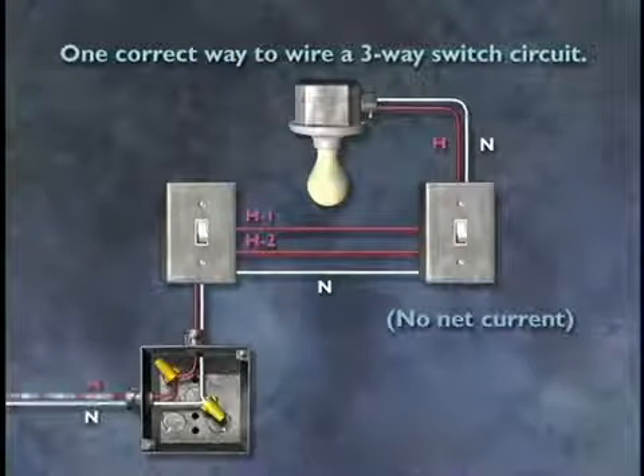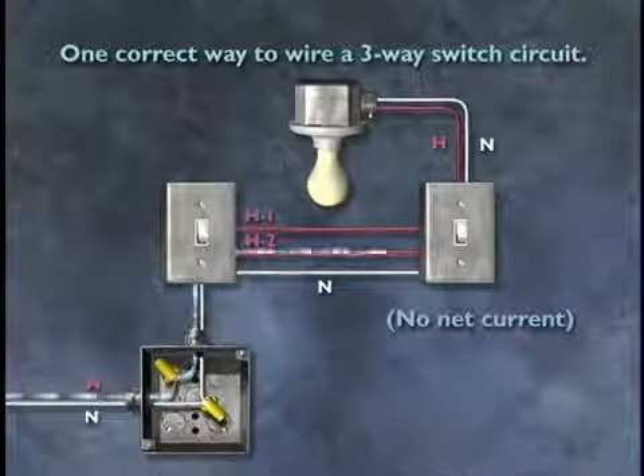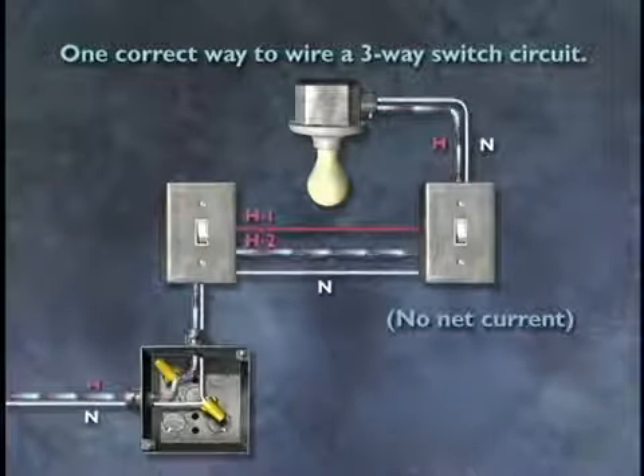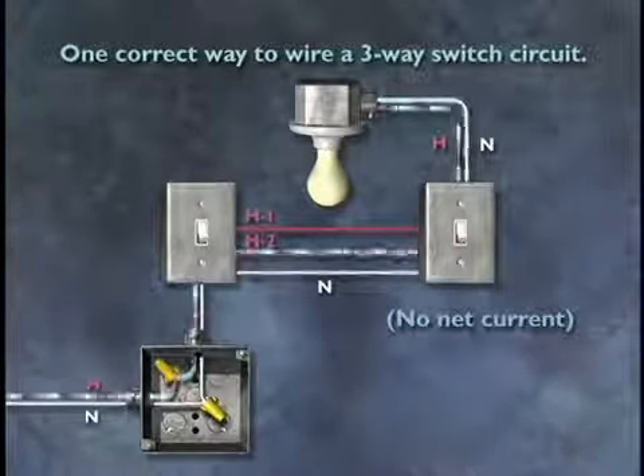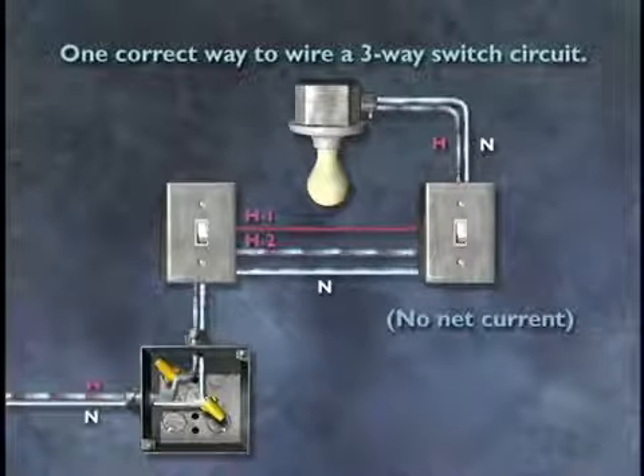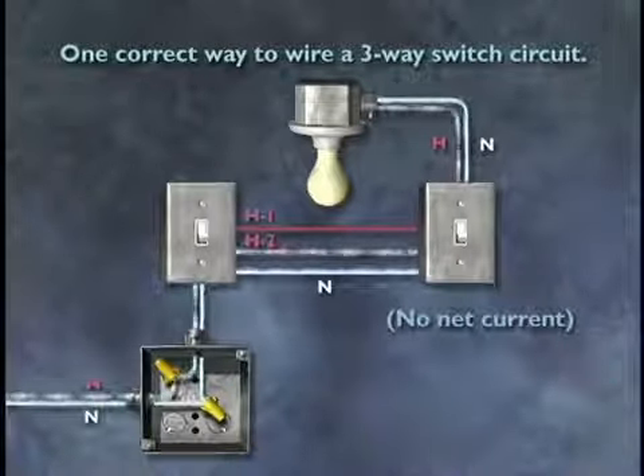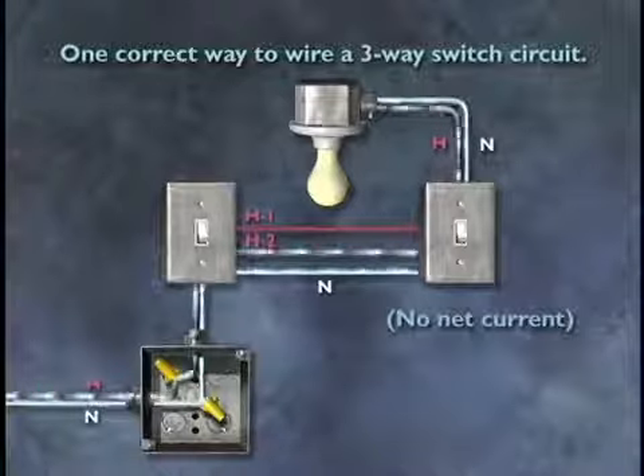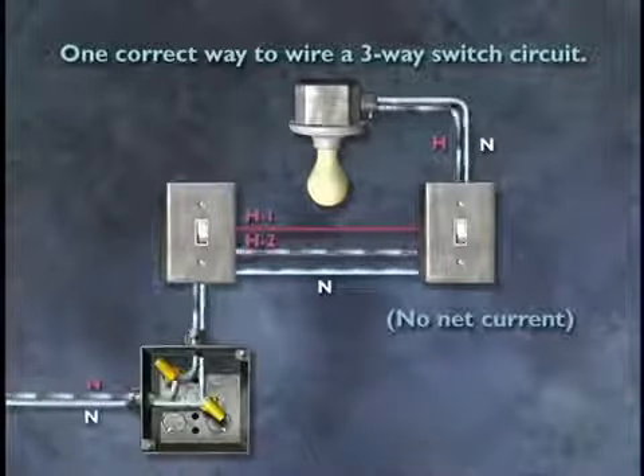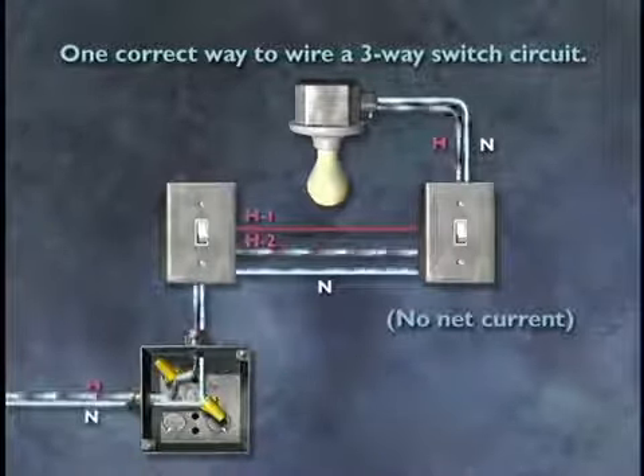First, we see a diagram of one correct way to wire a three-way switch circuit. As expected, the hot and neutral feed into switch 1. As you follow the paths of hot and neutral currents, note that at every run, there are two equal and opposite currents balancing each other out. Note that the traveler must have three conductors.